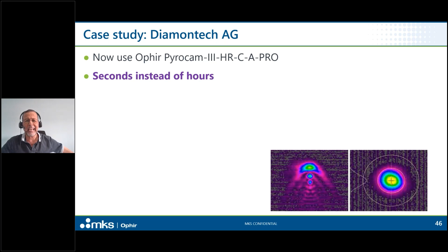Here's an example that they gave us, a new laser that they were performing incoming testing and analysis on. They wanted to integrate it in their systems, and they measured all sorts of parameters of it. The engineers could not get the beam to focus properly. Studying the beam profile showed that the collimating optics, one of these collimating lenses, was out of alignment. Once that was found, the laser supplier was easily able to fix the problem. You can see what it looks like on the right after alignment. Everybody's happy. And faster measurements obviously mean a much more efficient development cycle.